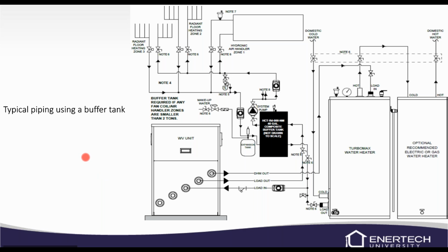This is a buffer tank setup. You're probably a little bit more familiar with the buffer tank setup. But again, it decouples for flow. So if you have an air handler that's smaller than 2 tons, we'd recommend that you use a 40-gallon buffer tank. Again, it decouples the pumping for your zones with the WV requirements.